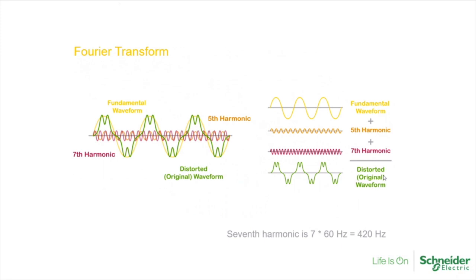And then a Fourier transform. This is what is used to analyze a wave shape and calculate your harmonics. This example is showing you that the yellow line is your fundamental, so that's your 60 hertz signal. And then they've injected a fifth harmonic and a seventh harmonic to create this distorted waveform. A harmonic is a multiple of your fundamental. We're using 60 hertz as an example because that's what the US system uses. So your fundamental will be 60 hertz, your second would be 120, and the seventh is going to be 420 hertz.